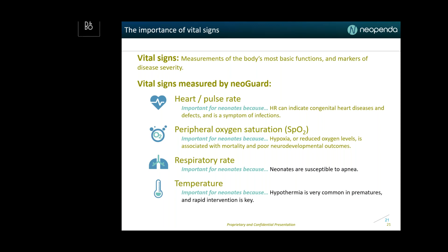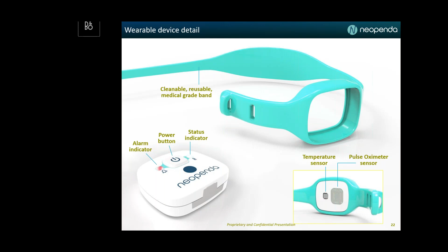This is again just more detail on the system. Many people with a biomedical engineering background are curious to know how it is that we detect all 4 vital signs. Well, we do this through 2 sensors. The pulse oximeter sensor is the one that gives us pulse, respiratory rate, and oxygen saturation. We've developed an algorithm that can deduce respiratory rate from the same capillary waveforms that are used to detect pulse and oxygen saturation. Then the temperature sensor measures temperature. It comes with a reusable band, and then the device can go in and out of the band so that these 2 units are cleaned separately. Next slide.